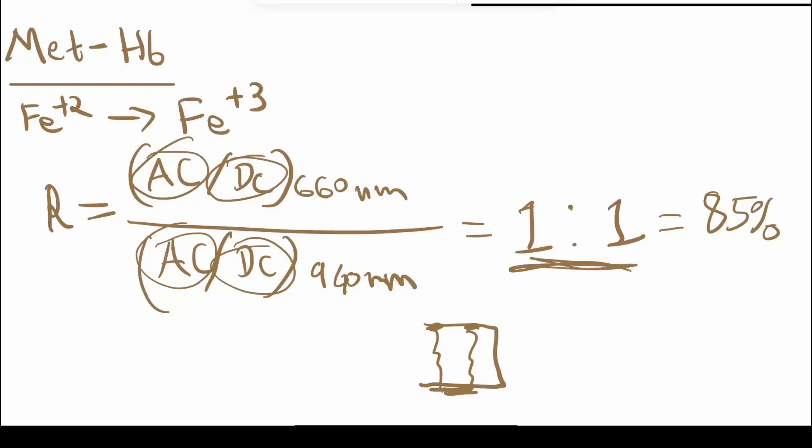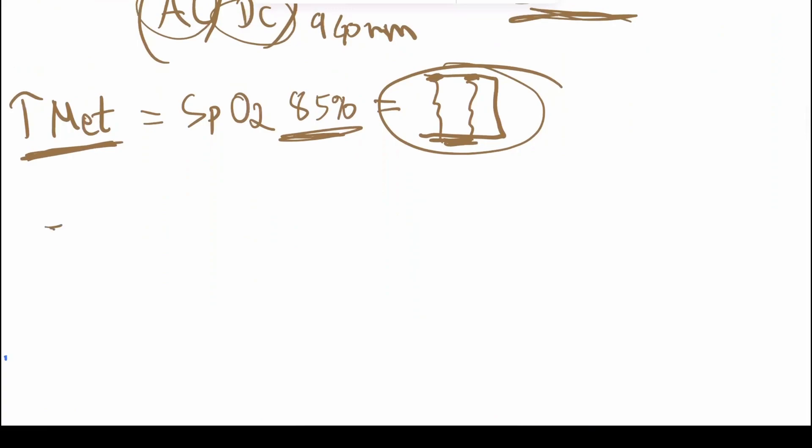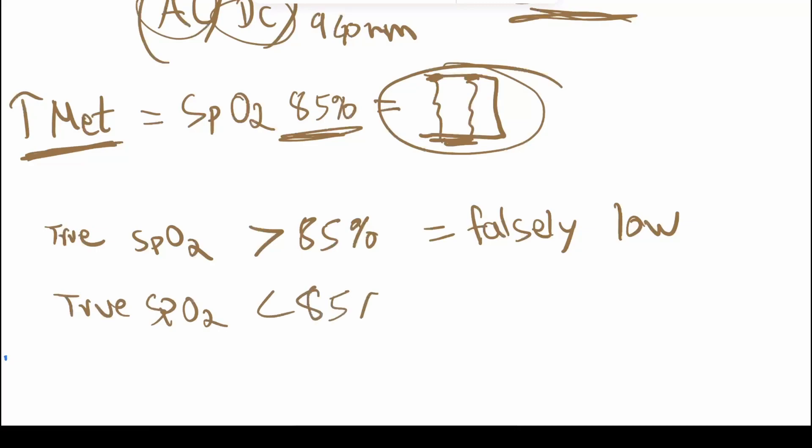This is the exact same thing that happens during methemoglobinemia. The increased amount of methemoglobin in your blood will cause the SpO2 to reach 85%. So increased methemoglobin or no finger will both result in a SpO2 of close to 85%. What this means is, in reality, if your true SpO2 was higher than 85%, then you have a falsely low reading. But if your true SpO2 was less than 85%, you'll have a falsely high reading.